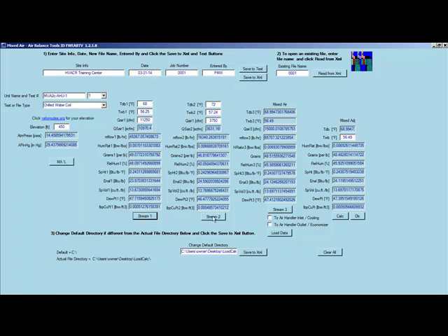So as we go through and calc these buttons out, the mixed air will enter a certain amount of data. So not all of these get populated at once. To be able to fine-tune this, what we need to do is match our grains, because at this point all we're doing is trying to match the grains, and as we increase or decrease this number, you can see our numbers will change.